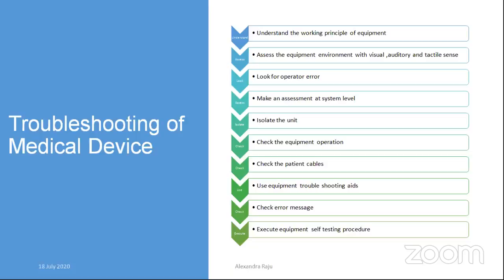There are leads. Some will be a three lead system, some will be five leads, or a 12 lead system will be available. There is a printer to print the ECG out. Some ECG machines are battery operated. So we have to understand the basics of that equipment which we are going to troubleshoot.